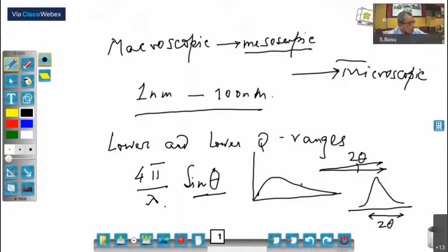We have to tighten the collimation of the beam to make the direct beam narrower. When you do that, you sacrifice neutrons. Secondly, when you go to longer wavelength, you don't have too many neutrons, so already you have a smaller number of neutrons, and then you are further reducing them by collimation, so you have intensity issues. That's why people use small angle scattering instruments on a cold neutron source.